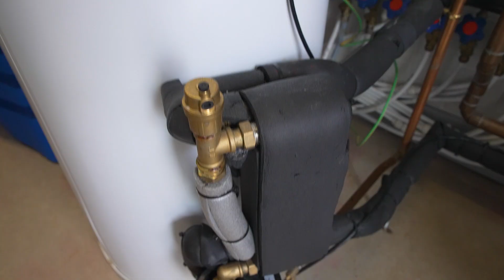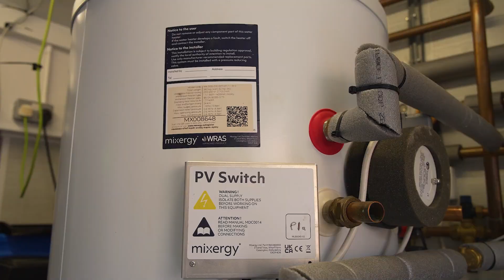That's more efficient anyway with cylinders because they stratify more, so it will keep the cooler water at the bottom, which is better for the heat pump, and the heat's at the top. The other wise decision about Mixergy, this is, so I don't know if Mixergy historically were the most efficient. They were certainly up there amongst the most efficient. In this scenario, I would have suggested Mixergy's because you're going to have an empty property sometimes and a completely full property other times, so Mixergy was absolutely the correct solution to go for in this property.